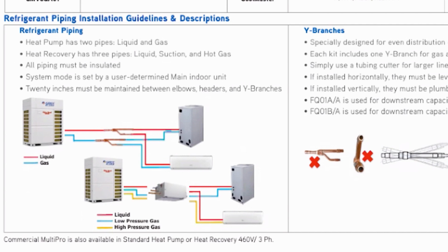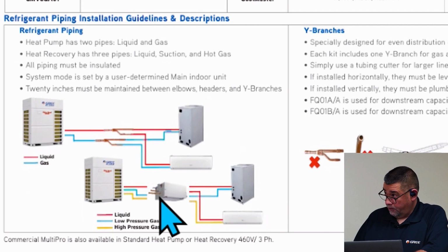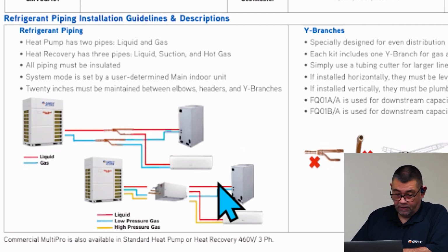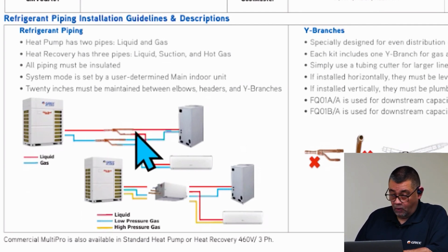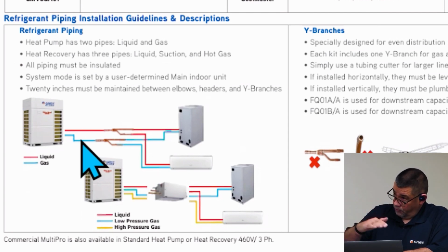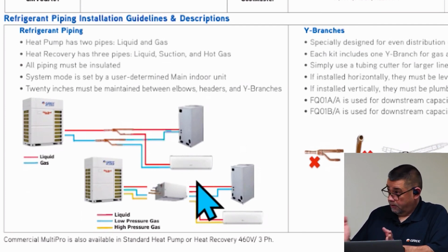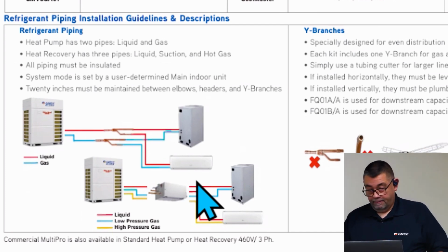The other thing on this diagram: you see there are two lines, one for liquid and one for gas. This diagram indicates a heat pump application. The bottom one you see here is a 3-pipe system, and it also has a mode changer in that illustration. Keep in mind that when we go into the selection software, it's only going to show one line coming out of the system. So you have to visualize that for a heat pump there's the return pipe, and for heat recovery there are two additional pipes - low pressure gas and high pressure gas - that you don't see in the software.